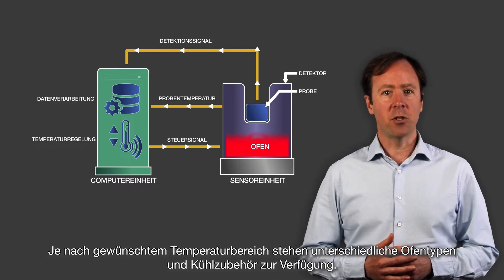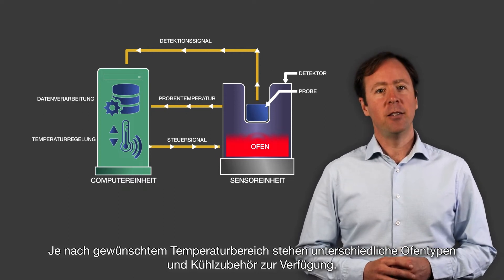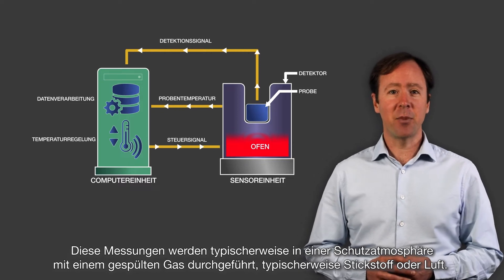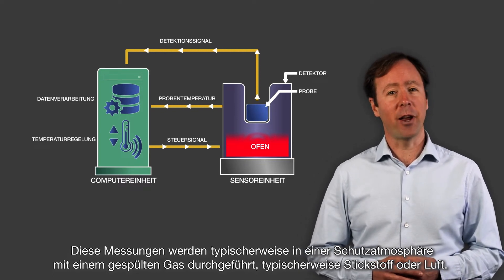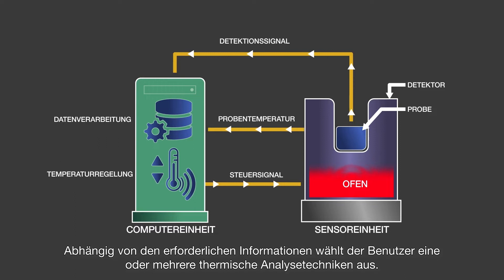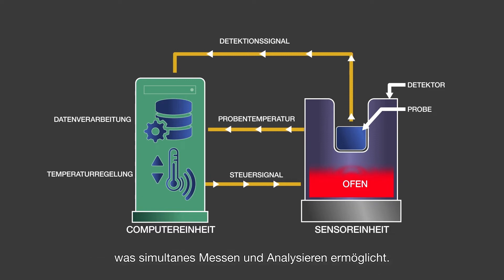Different types of furnaces and cooling accessories are available depending on the required temperature range. These measurements are typically done in a controlled atmosphere using purge gas, typically consisting of nitrogen or air. The temperature control, data recording and analysis are all computer controlled. Depending on the information required, the user will select one or multiple thermal analysis techniques. The computer can be connected to several instruments which have other types of measuring techniques, enabling simultaneous measuring and analysis.